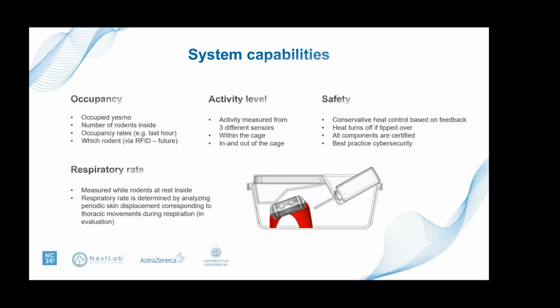Then we have a very conservative heating based on feedback. And of course, if it was to tip over, I think the rats, if they really, really want to, they can probably at least move it. But then it will turn off the heating. We also have certifications for all components. So FDA certified material, for example, electronic certified, Bluetooth certified, and cybersecurity considerations. So it becomes not a fully medical device because it doesn't need certification by a notified body, but it follows all the safety standards that we normally do for a medical product. And of course, it can be reprocessed, so cleaning and disinfection is supported.